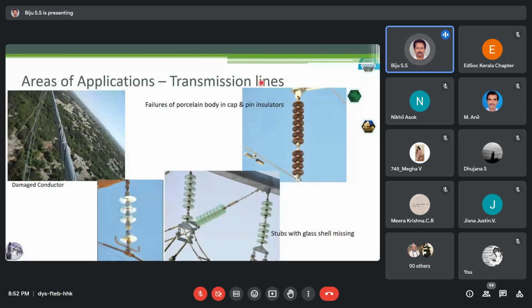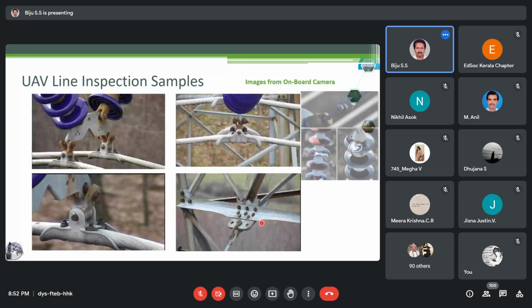I'll show you results. This is a shot of failure of a porcelain body just detected by the UAV. Damaged conductor is also there. Then there is a disc failure. Some discs are missing. These things can be identified by the UAV inspection. Again, corroded clamps, corrosion can be detected very easily. See, damage to the insulator can be detected very fast.